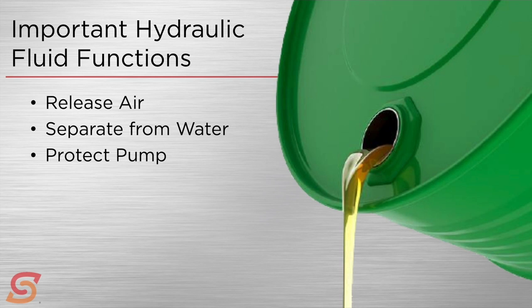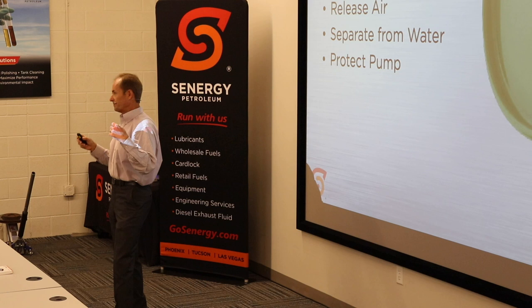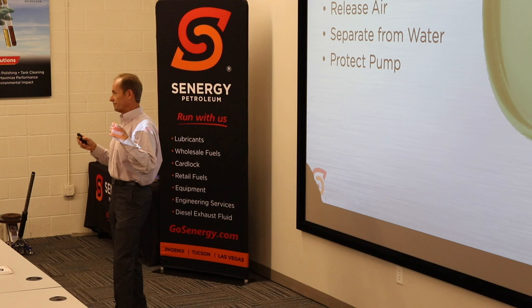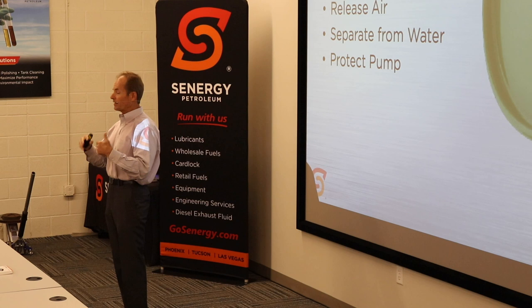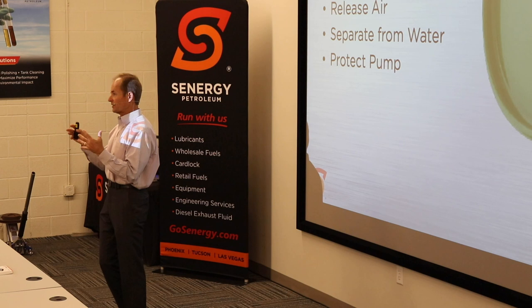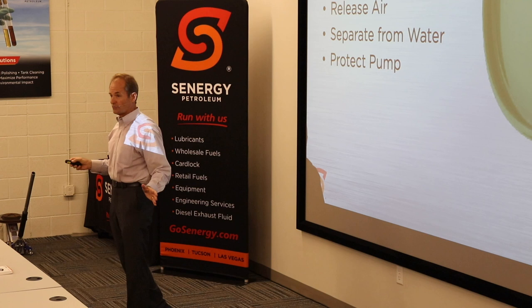We also want to be able to protect the pump. The pump is the biggest metal-to-metal possibility going on in a hydraulic system. There are a bunch of different pump designs — I could put on a two-day class just talking about hydraulic pumps. Particularly the higher the pressure, the more metal-to-metal contact is going on inside the pump, and so the more we need to protect it from wear — we're going to count on the oil to do that for us.